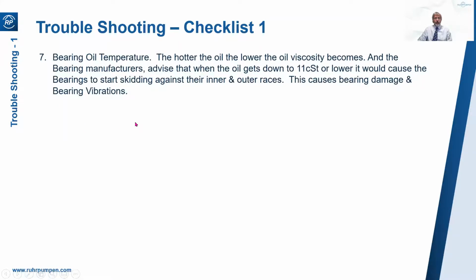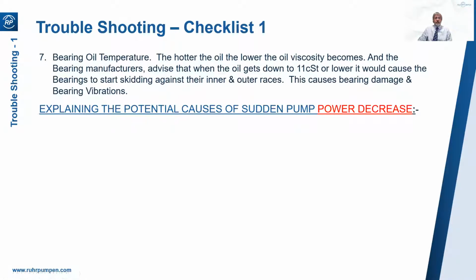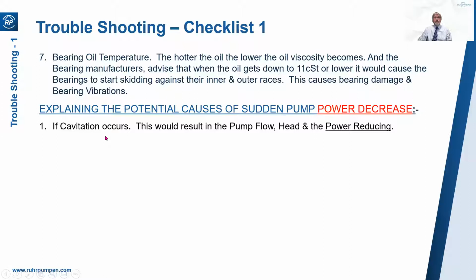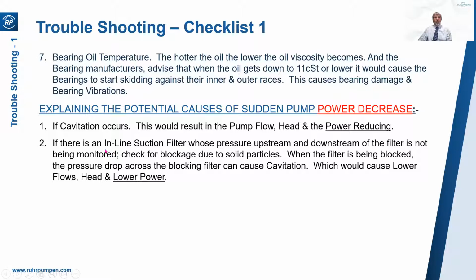Now, power decrease. Cavitation. Okay, if you've got cavitation, you're going to get lower pump flow, lower pump head, and hence the power will reduce. You're obviously going to have vibration. You'll also have that telltale sound that sounds as if somebody's put a handful of gravel in the suction of the pump. Perhaps you have an inline suction filter not being monitored. Check for blockage. If it's blocked, you'll be restricting the flow. It could be causing cavitation, but either way, you've got low flow, low head, lower power.